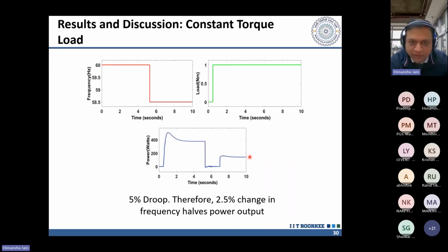Unlike a generator, where we would increase our power output, here we are reducing our power demand to get a quick response for the grid. This is something we are now working on validating in hardware. We find it really attractive because we don't need any communication infrastructure to make this kind of load change or create this kind of flexibility in our system. These are some of the things at faster timescales that we are working on in terms of getting flexibility from resources, which is not something we generally talk about whenever we talk about demand response.